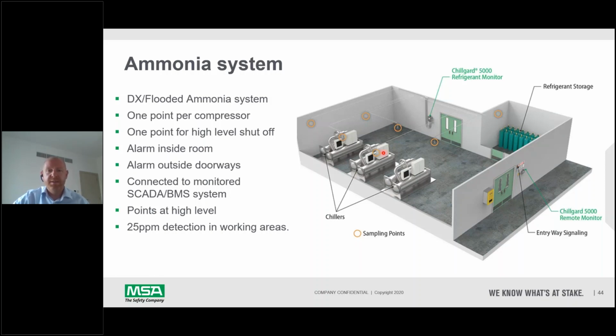So one point per compressor for a flooded or DX ammonia system. And then we need one point as well for high level shutoff as per the standards. Alarm inside, alarm outside, and then of course connected to the central BMS system to let the main operator know there's a leak.